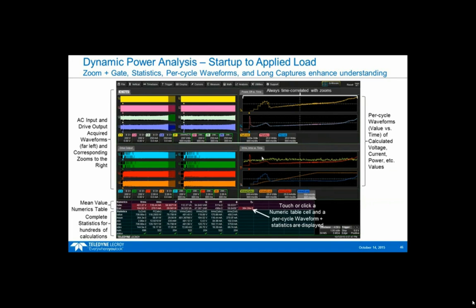So I've now got 7 waveforms created, and the waveform is defined by the intersection of the measurement type and the source - so VRMS and sum ABC. If I look over here, I have a waveform that says VRMS sum ABC, it's green, this waveform right here, showing me what the voltage value is changing over time. That's pretty constant - it's nominally 481 volts, and it's pretty steady.